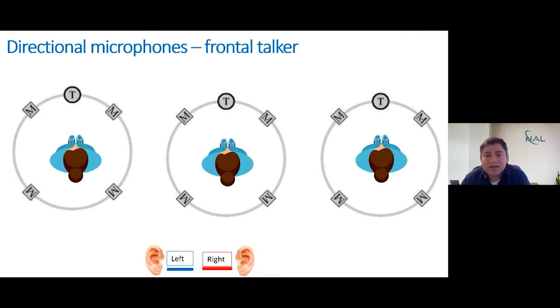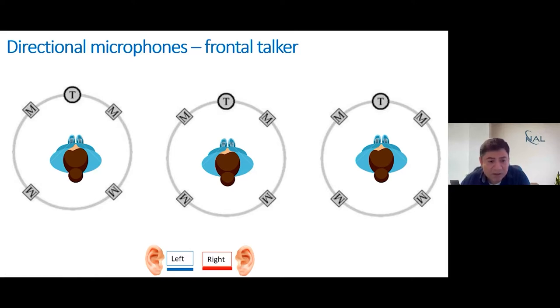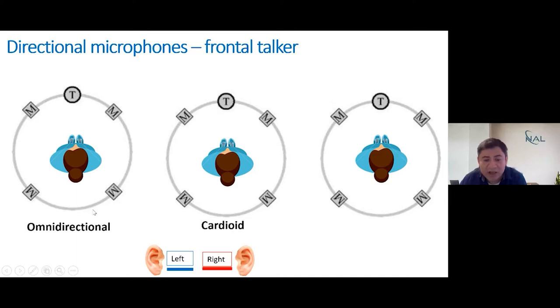What we have here is a typical conventional laboratory experiment setup where we have a listener sitting in the middle of an array, with a number of sound sources positioned around the listener. We have a target location represented by a loudspeaker, and noise sources around it. We typically fit hearing aids to the patients on the left and right, and then evaluate performance — comparing omnidirectional and more directional systems like cardioid and beamformer formats.